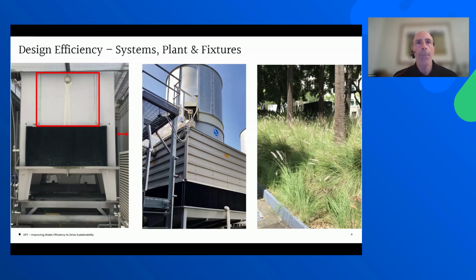Other things I haven't shown in here, but what we find on a similar design issue, is making sure that you don't have very long runs of return pipework located above the height of the basin, because when the pumps shut down, you can see water flooding back into the tower, and we see a lot of water lost via overflow. And with respect to enclosures, you want to make sure that the discharge is protruding well above any enclosures and walls. Otherwise, you run the risk of short cycling, with exhaust air coming back into the air intake side.